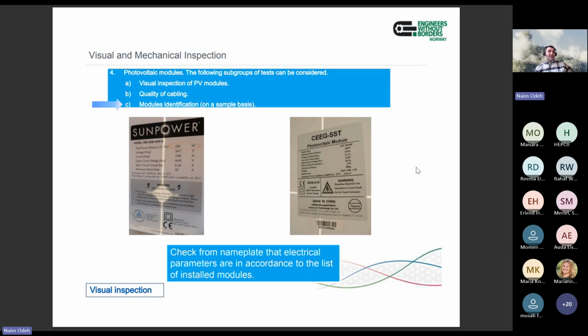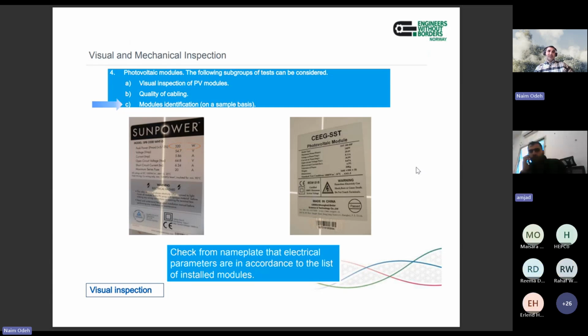Also, if there is a mismatch, if there is any wrong module installed in the middle of the correct modules for any reason, sorry guys. Yeah, so it's not about trust or not. Maybe by mistake, one wrong module is installed in the middle of correct modules. If you have 100 or 200 modules installed for multiple strings, all correct except one module installed in the middle that doesn't match these modules, this will cause a lot of problems later on. So it is your responsibility as a testing engineer to find this and to verify it.